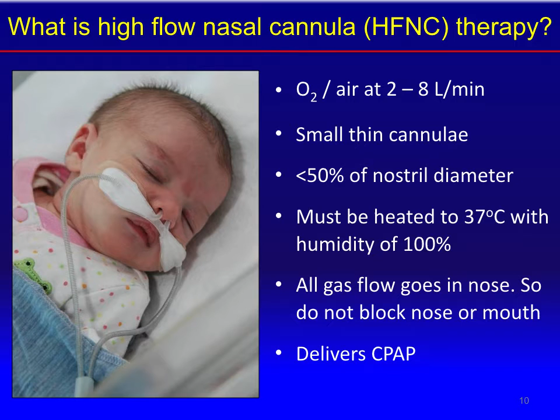The other thing you have to remember with high flow, it's not like CPAP, which has got an expiratory valve on the ventilator or a bubbly bottle where the excess gas, as it were, is being vented. All the gas, all that flow, let's say it's 6 litres, going in through the equipment, goes into the nose and must come out again. And please, please do not block the mouth and the nose, otherwise there's going to be a nasty mess all over the nursery. It's a lot of gas coming in, it must come out, and that's one of the reasons that the prongs need to be small.